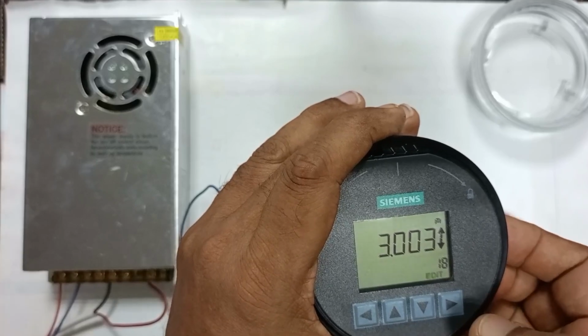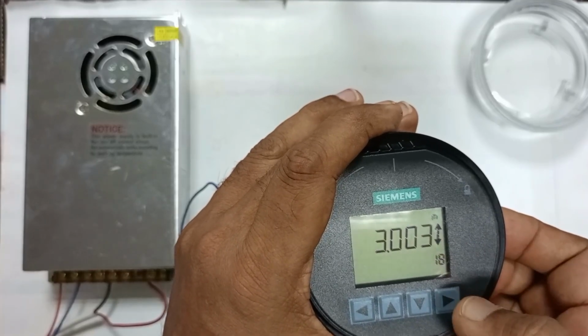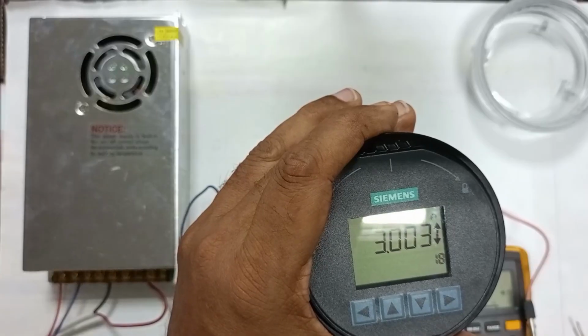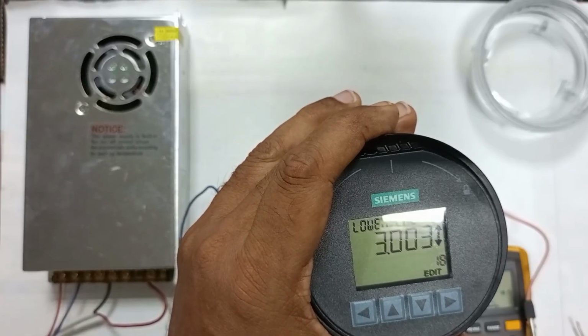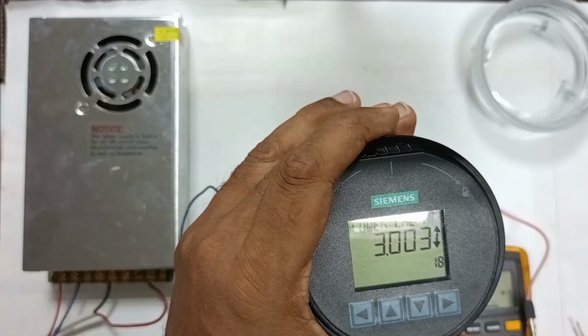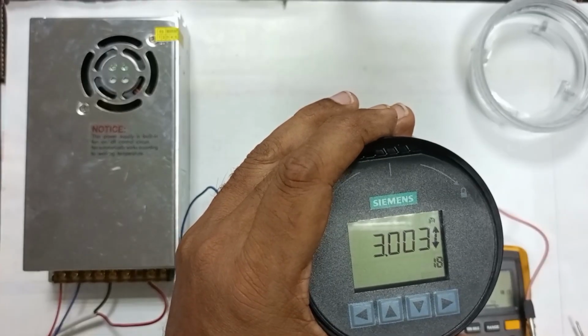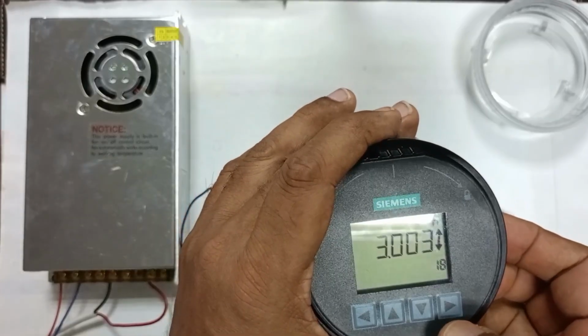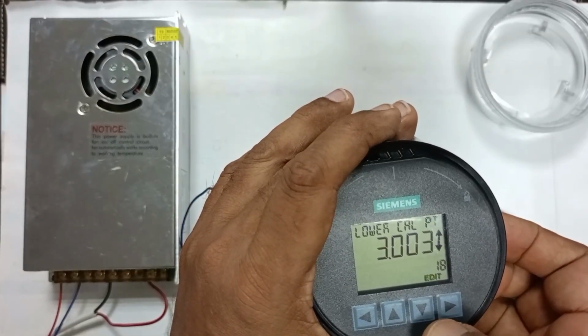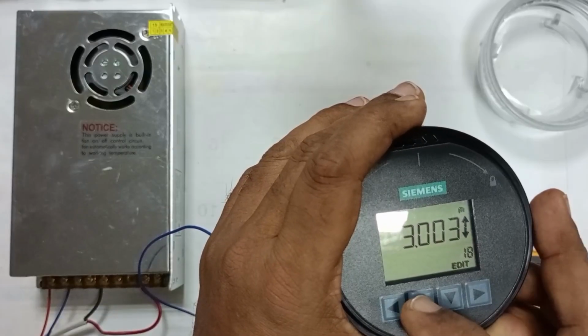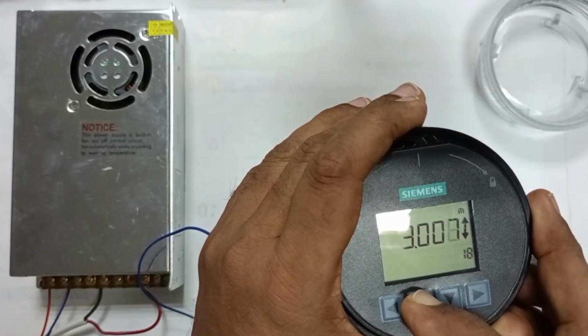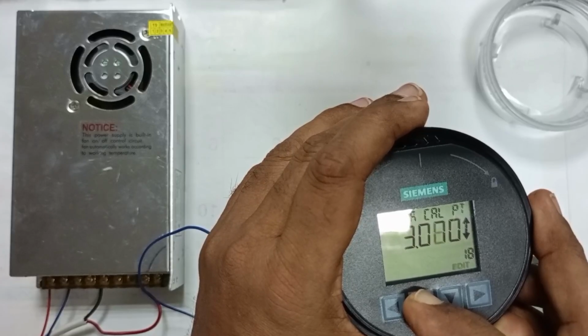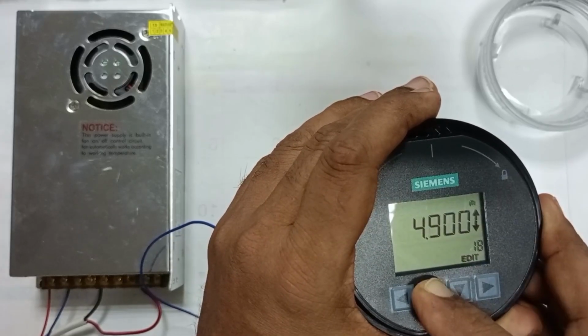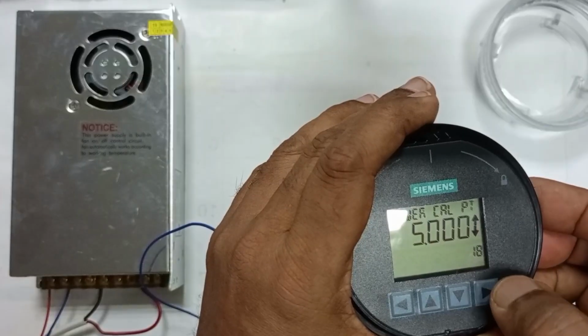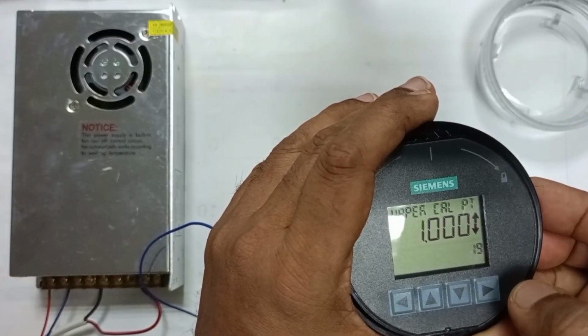We will set here the lower calibration point. We will measure a 5 meter tank. So the lower value will be 5. That means when the liquid level is at the lower side, that is minimum, then the distance for our tank is 5 meters. Lower value we will use 5 meter. Okay, you see this is increasing, 3.5 meter. Okay, this is the lower value. Now we set this value.